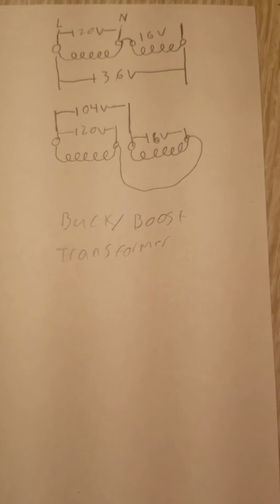One might be for voltage drop. You have a long run and you end up having lost, say, 5 or 10 volts at the end of it. It's too low to safely run your equipment, but you don't want to have to buy a full big transformer just to step your voltage up by a few volts. So with an auto transformer, because you're only actually having to transform a portion of the current, you're able to get away with a smaller and cheaper transformer while still being able to deliver power the way that you need to.